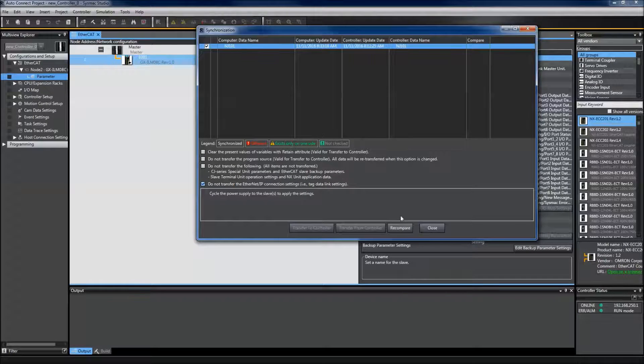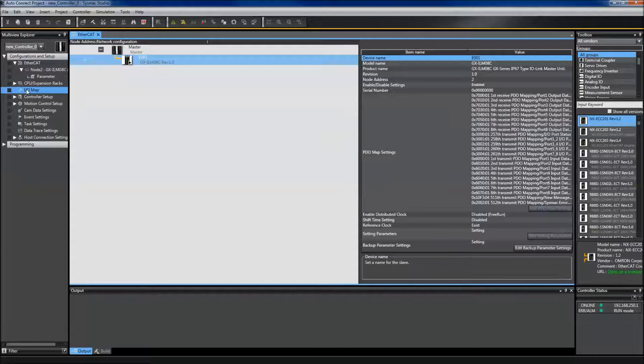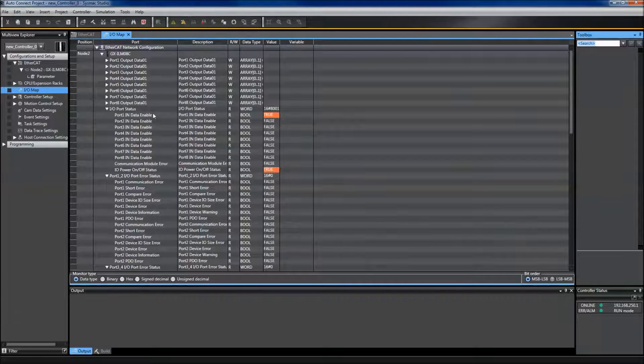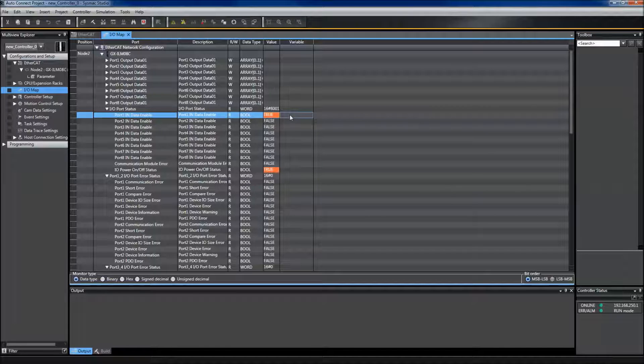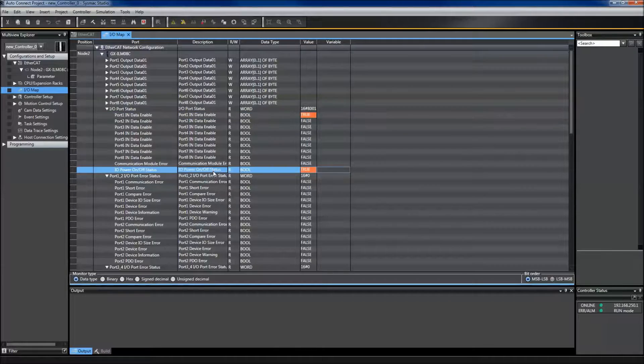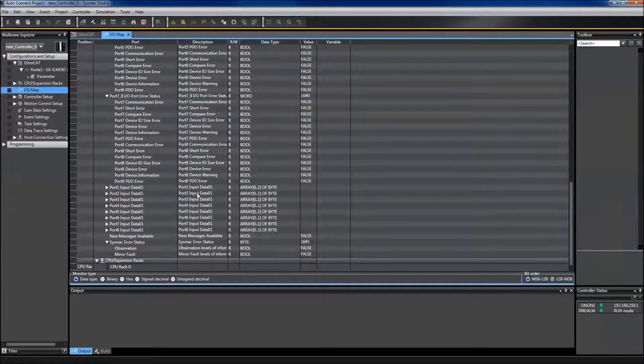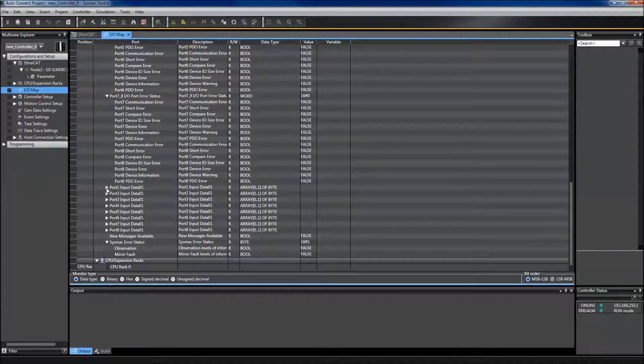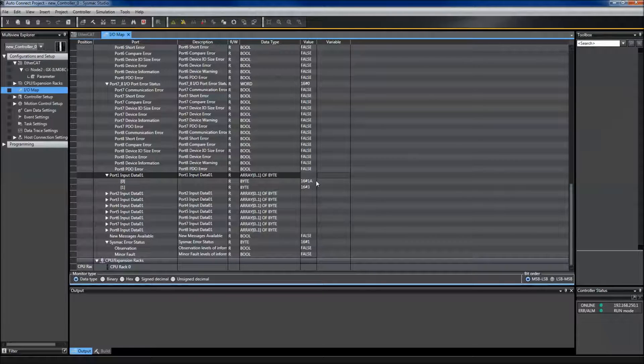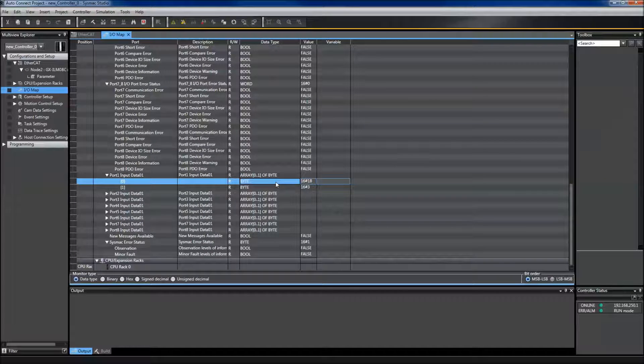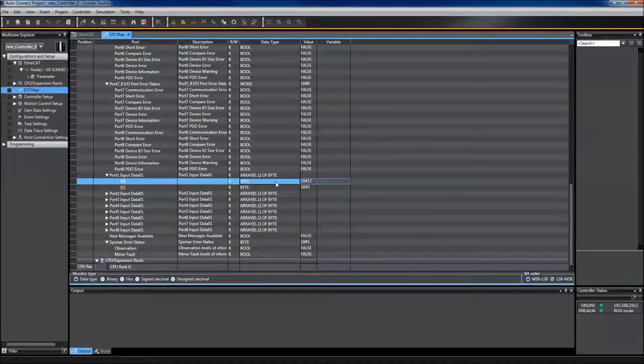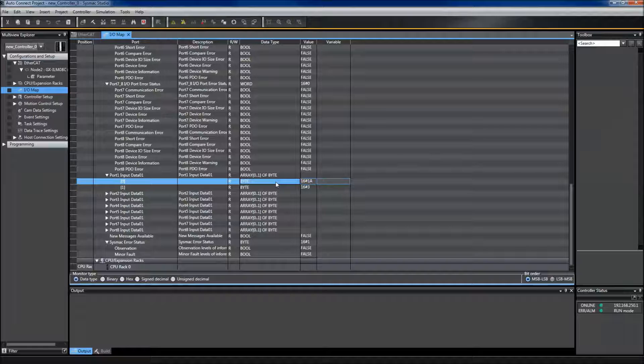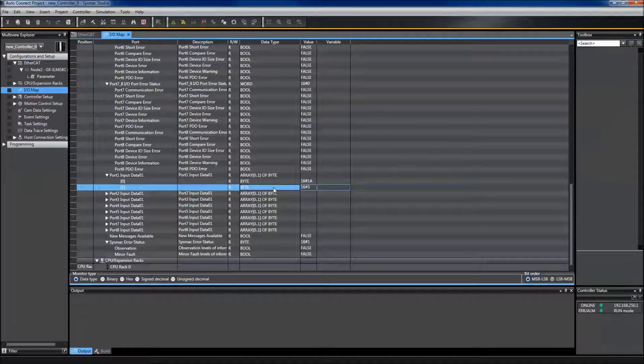Now that everything is transferred, you can close that box and go and check the IO data that I'm receiving from my device. I see that port 1 is enabled because I have an IO-Link device plugged into it. My power is on, and I can double-check the data I'm receiving from my IO-Link device. You can see the first byte changing. This is the monitored output according to the index list that you receive with your IO-Link device. The second byte in this instance is status bits that you can check.